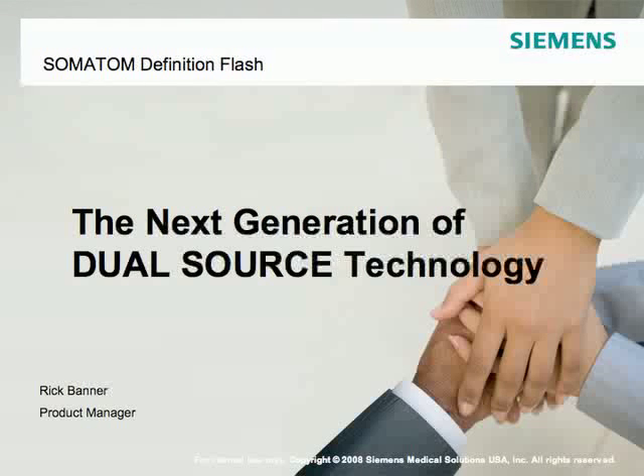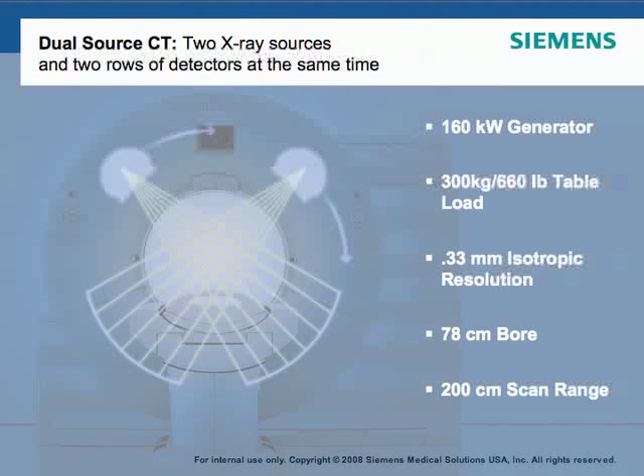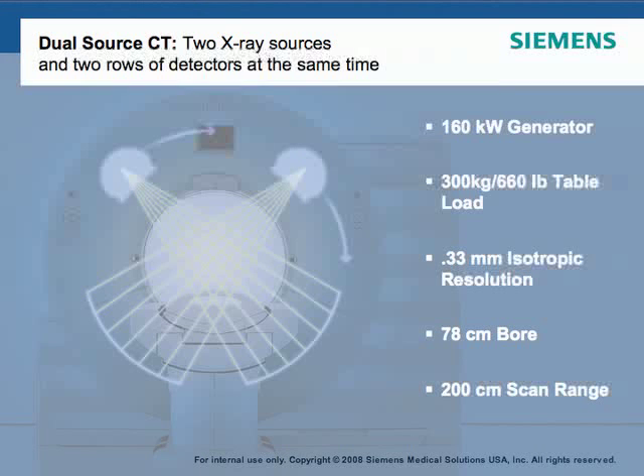The dual source CT was introduced back in 2005. The benefit was two x-ray sources and two rows of detectors acquiring data simultaneously. This allowed use of two kilowatt generators at 80 kW each combined into one, a 78-centimeter bore, 660-pound table for large patients, isotropic resolution down to 0.33 millimeters on all sides, and a 200-centimeter scan range.